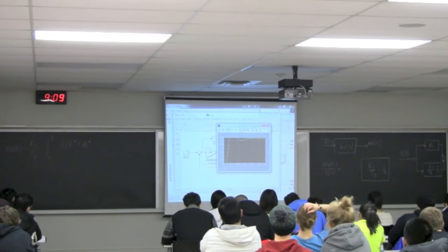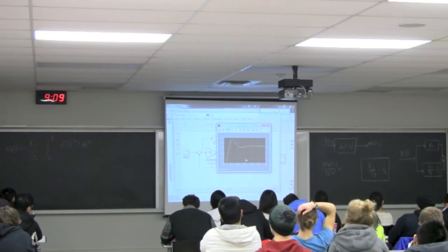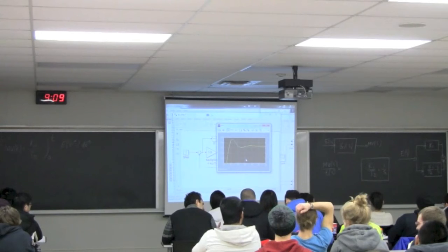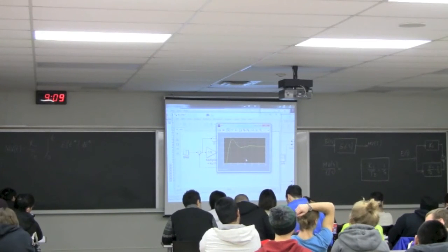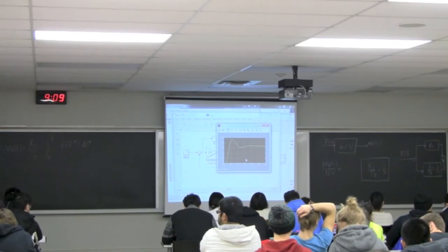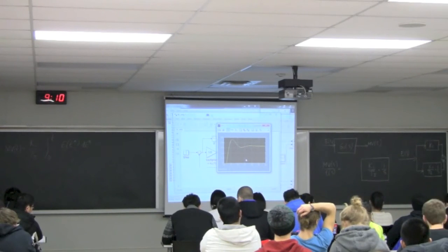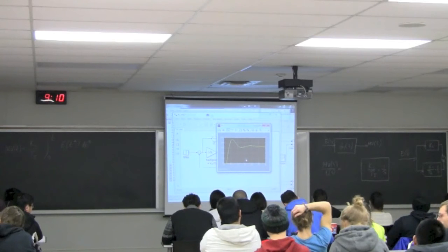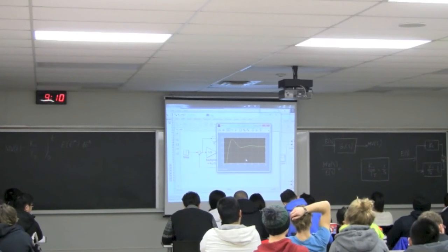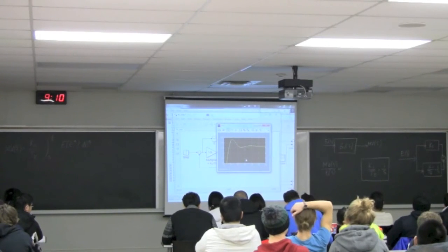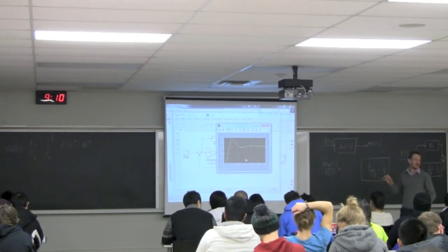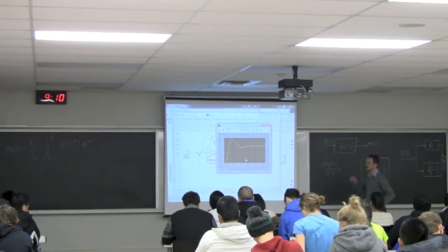Now let's take a look at that. What's happened there? So TI being lowered means we're going to take that error, that integral area under the curve, and instead of dividing it by 20, we're dividing it by 5, a smaller number. When we were dividing it by 20, we were dividing by a bigger number, so we were discounting the area a bit more and taking slower action. Now we're taking faster action because we're dividing through by a smaller TI.